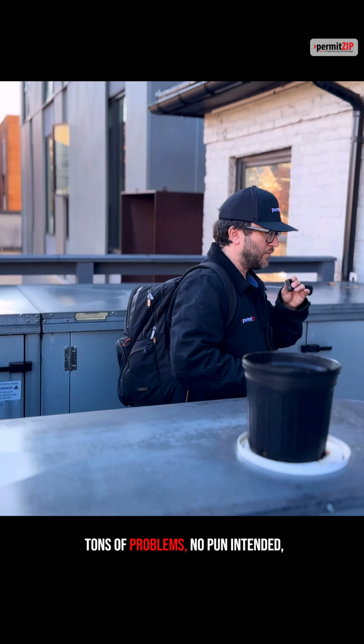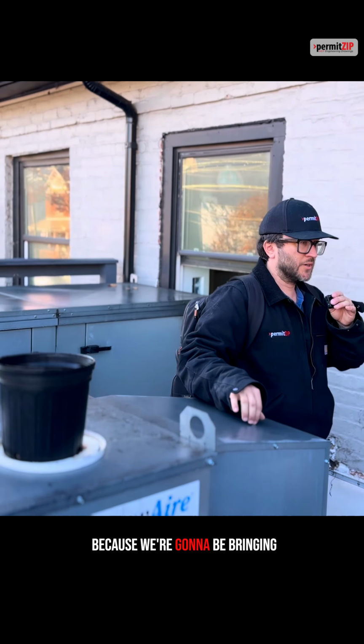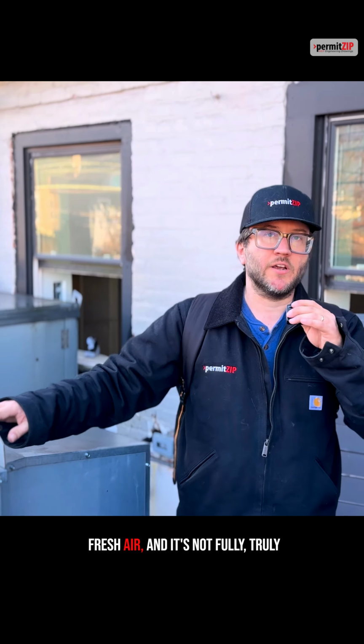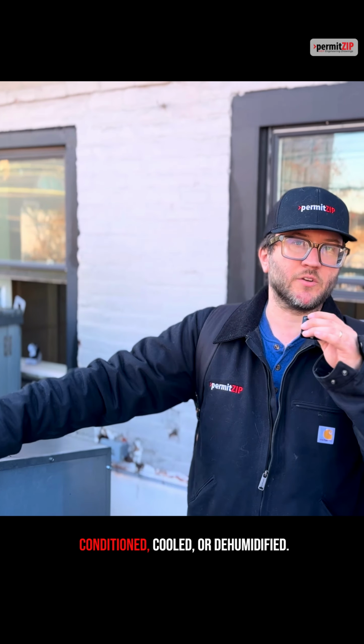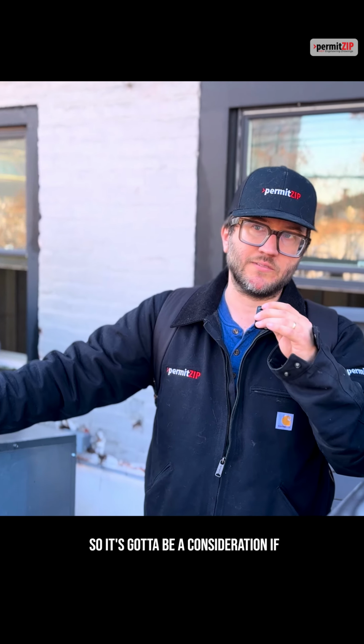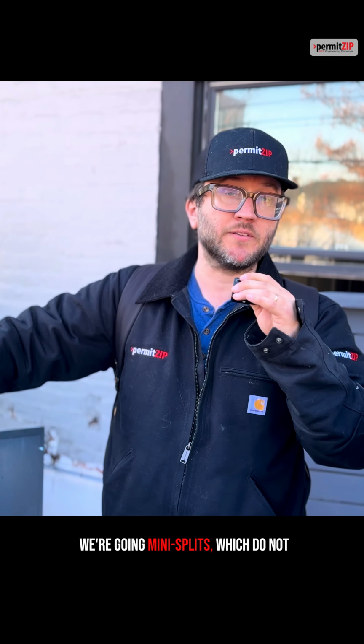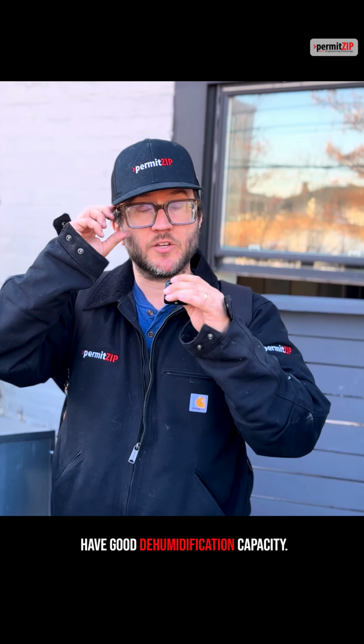Presents tons of problems, no pun intended, because we're going to be bringing in a lot of moisture with all that fresh air, and it's not fully truly conditioned, cooled, or dehumidified. So it's got to be a consideration if we're going mini splits, which do not have good dehumidification capacity.